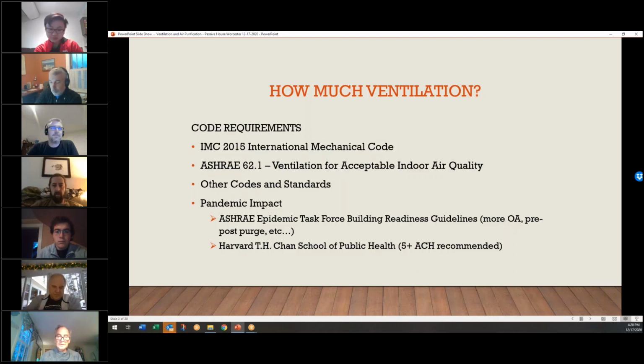And another document that has been referenced and used is from the Harvard T.H. Chan School of Public Health, which is talking about pandemic levels again. And they recommend 5+ air changes per hour in a space, which is actually a lot of outside air. If you figure a typical office building, 5 air changes an hour might be the equivalent of 1 CFM a square foot, basically your full supply air. So they're basically recommending that it should be 100% outside air during this pandemic mode.